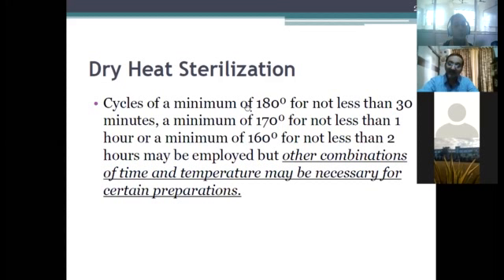Now this is an issue, and therefore industry changed these parameters, and in the tunnel sterilizers they are using a temperature not less than 250 degrees centigrade. All radiant heat tunnel sterilizers do not operate at a temperature below 250. Very high temperatures. Why? Because at that temperature, we have two benefits. Sterilization is also taking place. Depyrogenation is also taking place. So the products are safe, right? So that is why all the pharmacopoeias are saying that other combinations of time and temperature may be necessary for certain preparations. These are certain basics which we need to understand because we are deviating from the normal cycle, and therefore we have to validate our process, and we have to ensure that it is having the required sterility assurance level.